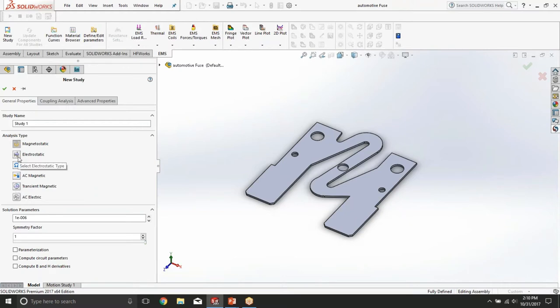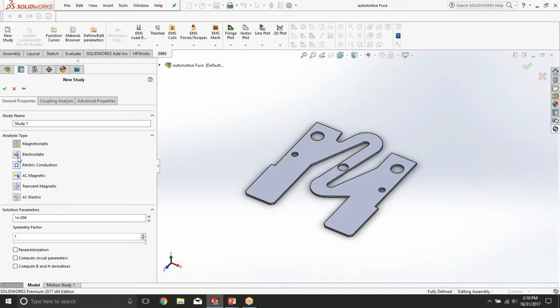Electrostatic study is a type of study that allows you to compute electric field distribution and it's very useful for computing dielectric breakdowns. It's widely used in bushing design or power insulator design, in any application where you really want to know the electric field intensity. And finally we have AC electric study which allows you to compute currents induced by the changing electric field.